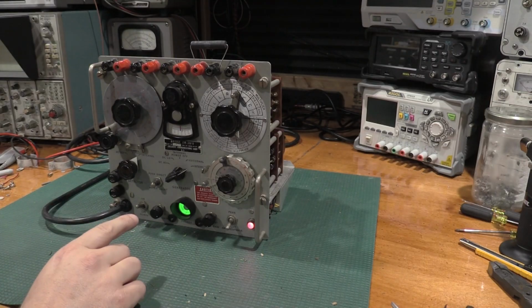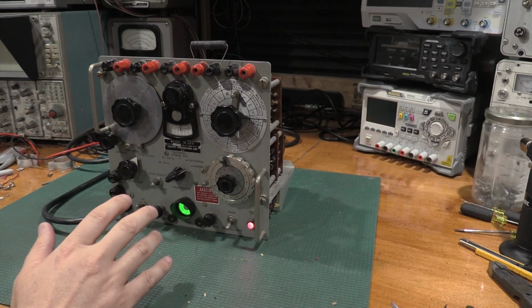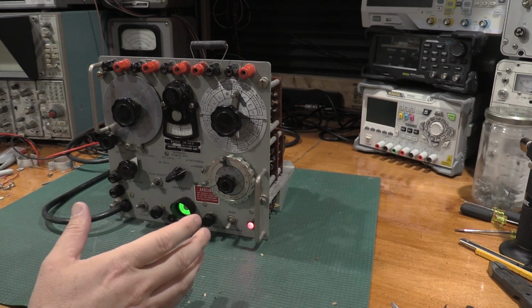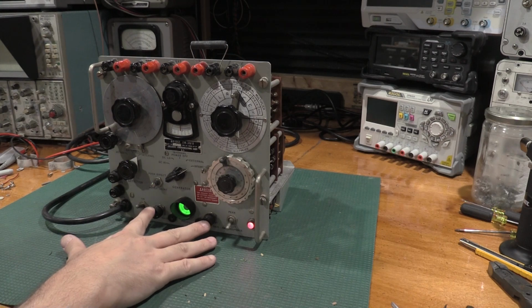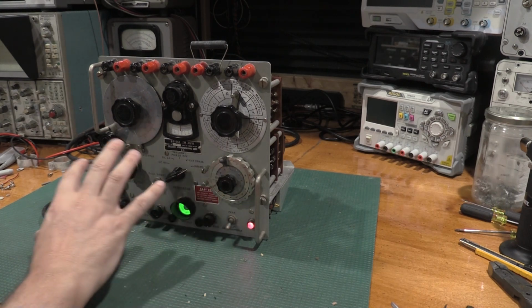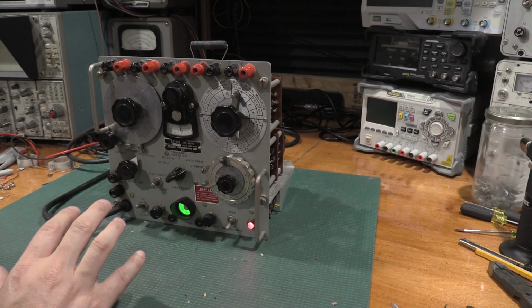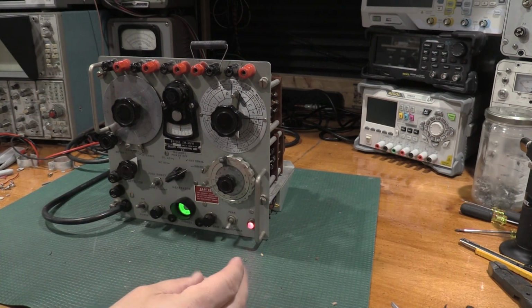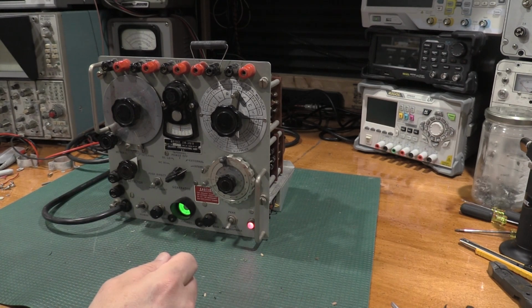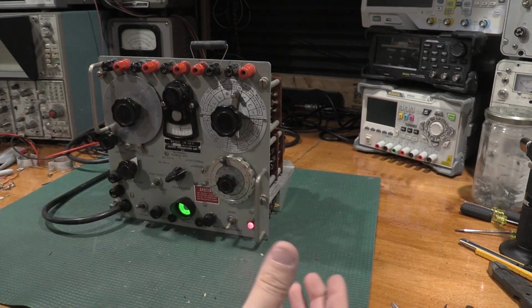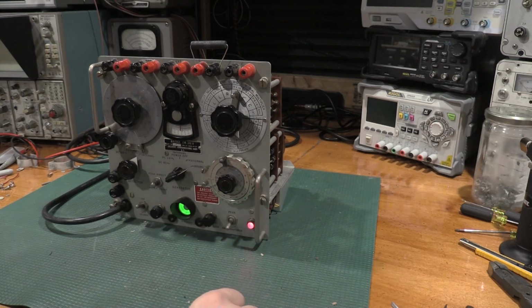One thing to note about this unit is I ran through the manual, and unless I missed something, there are no potentiometers or anything to adjust. There's some front potentiometers, but there's no calibration points in this unit. Some test gear like this has accuracy that is considered intrinsic to the design, and because of the way the unit was designed, that's the accuracy we get.